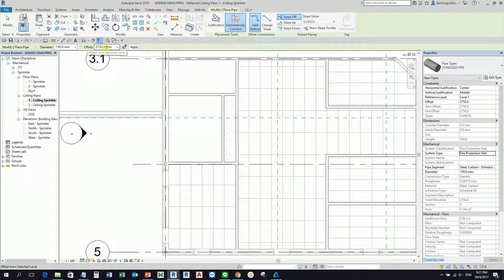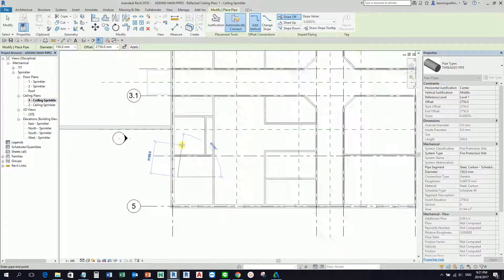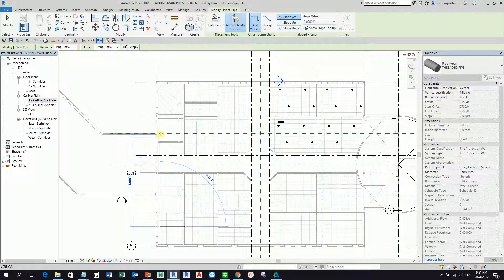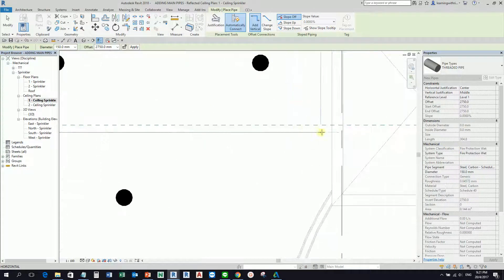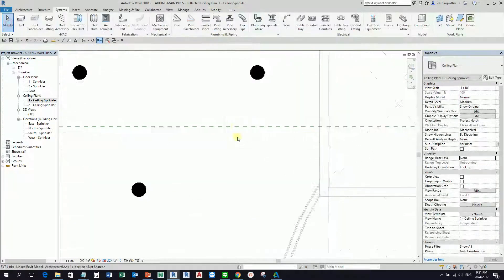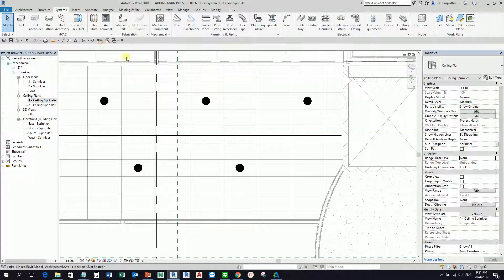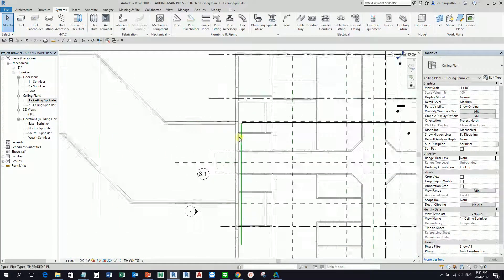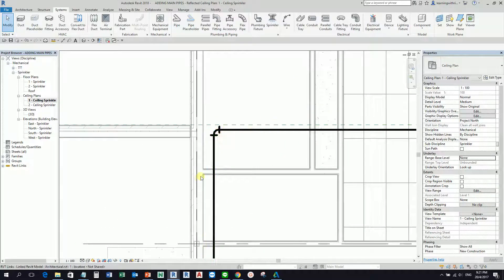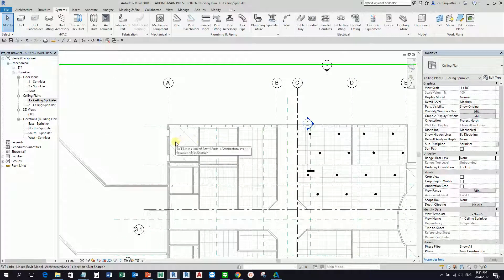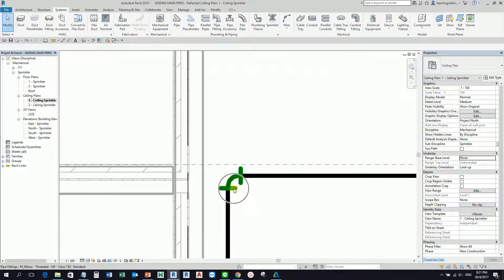I'll select 150mm and start drawing. I'll use 2750 as the offset height for my pipe. I'll pick a start point here, then pick another point here, and select Modify. Let me turn off thin lines to show the thickness of the pipe. The pipe is showing as a single line because of the detail level — you can change that to see the 3D view of your pipe.